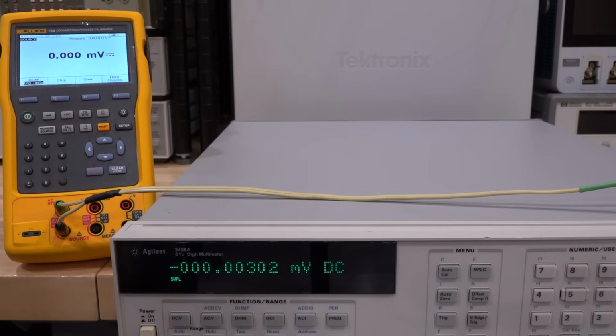Now before we dig into it too much, let's see if it measures voltage correctly, because it did pass the voltage calibration test. So I have it directly connected to the Fluke 754, which is a process calibrator. We can synthesize voltages, currents, and resistances with this pretty accurately and precisely. So right now it's set to 0 volts, and this is measuring roughly 0 volt, which is a good sign. Let's try 1 volt, for example. 1 volt, and yeah, look at that. That's pretty good, I would say.